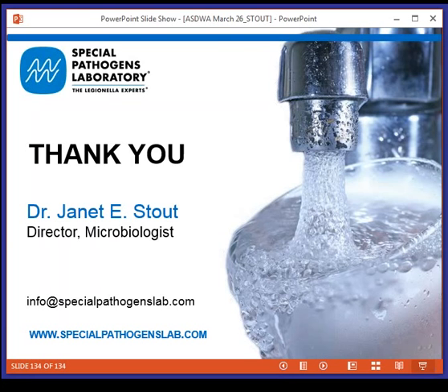Well, because we've been, over these 30 years, trying everything, we also evaluated ultraviolet light in building water systems. And this is what we found. If you put the UV light on the water coming into the floor, for example, in a hospital wing, and you turn it on, you are going to have no effect downstream. So you might be disinfecting the water coming through the unit, but all the fixtures, all the faucets and showers and pipe downstream, Legionella is living happily ever after. So what we did was we put the UV unit on, and then we did a shock chlorine disinfection. So we disinfected the downstream piping and ran the UV unit.